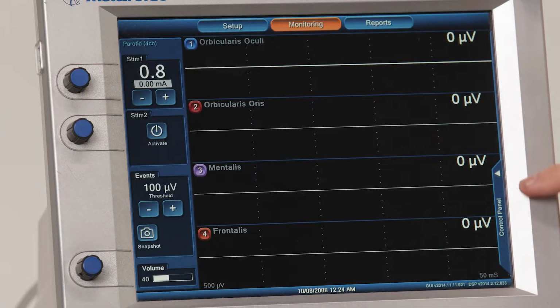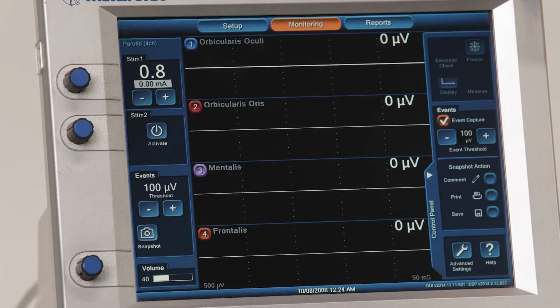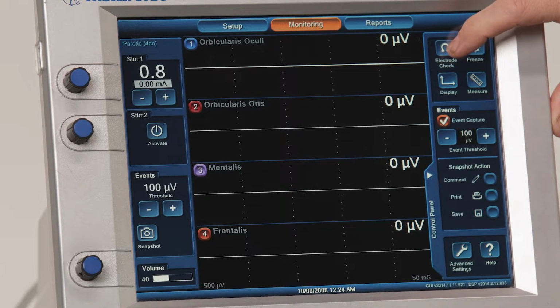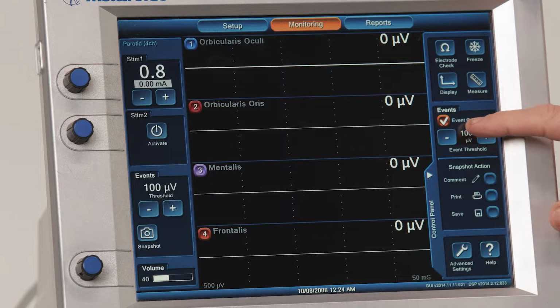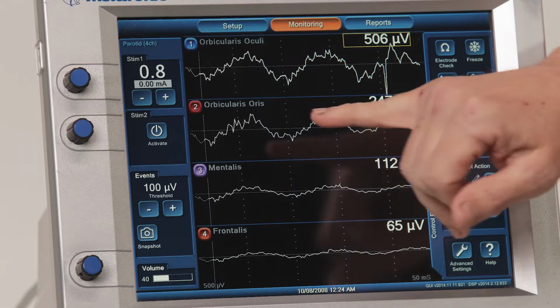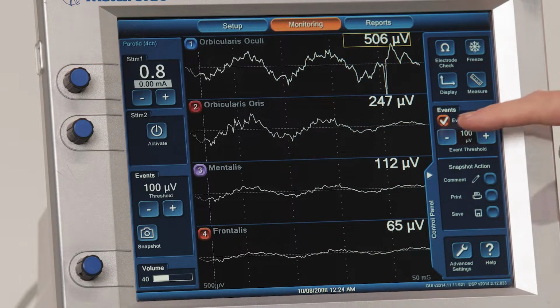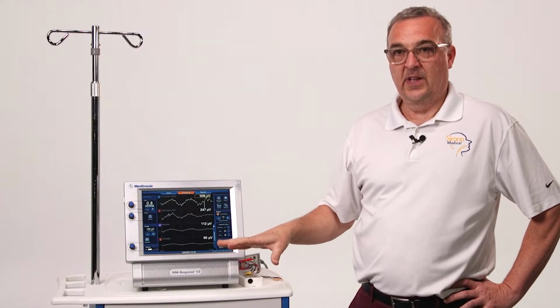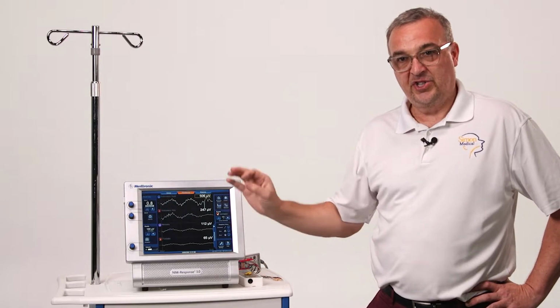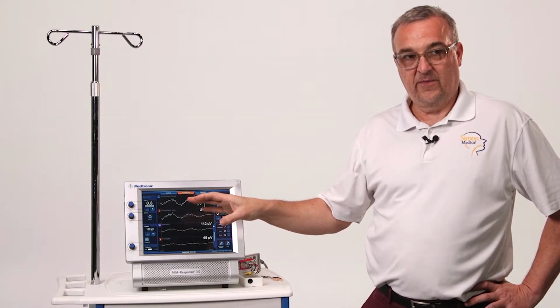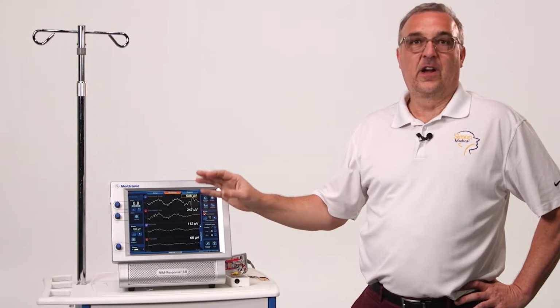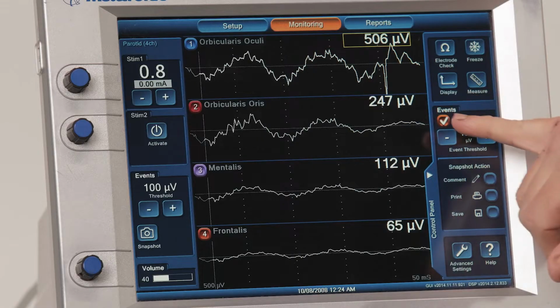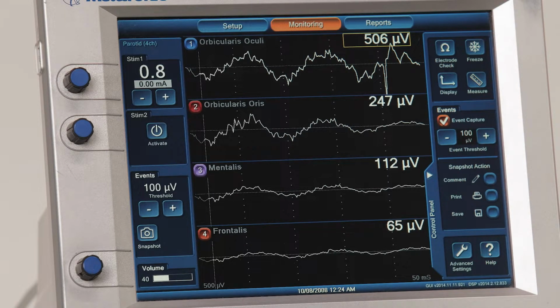I'm going to show you the control panel and all the settings. It's a little bit hidden here, but if you see control panel, touch that. Okay, you can go back and check your electrodes again. The event capture should always be on. I'll give you an example of that right now. Touch that. It's going to save whatever events come up. If I turn off event capture, that's going to go away and it's only going to be real time. So you're not going to be able to turn and look and see what channel, what nerve we set off the alarm with. So I would never deactivate event capture, okay?